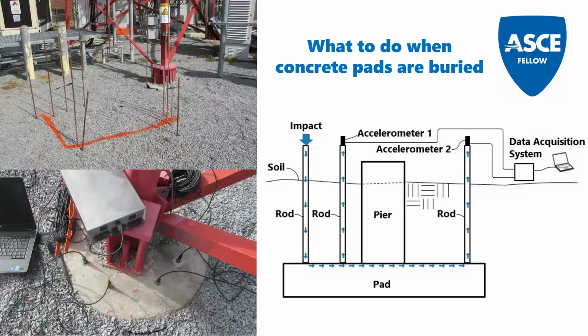Then you can come over and drill you some holes or drive you some rods, put a transducer on your rod, and take a third rod and hit it with an impact device, a hammer. These are 8-foot grounding rods that you can get from Home Depot. And it creates the pulse in this buried pad. And you can measure the waves with these transducers, and you can get the thickness of the pad.